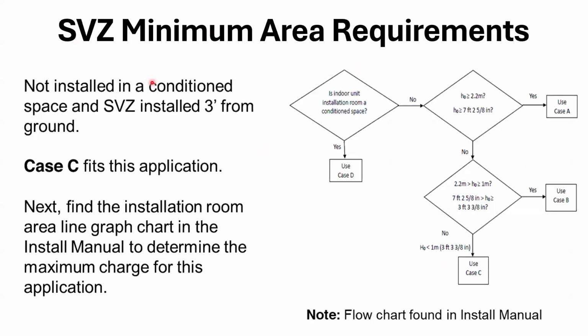Here are the requirements right here. Not installed in a conditioned space, SVZ installed 3 feet from the ground. And they have the dreaded flow chart that everybody loves, but that's what you would follow right here. Is the indoor unit installed room a conditioned space? No. Then we go over here, and this is tough to read what they're asking. Basically, they're asking from the floor to the bottom of the unit, is it greater than 7 feet 2 inches, let's just say?